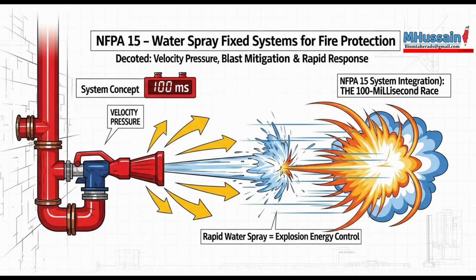It really is. What specific type of event are these UHS systems designed for? UHS systems have a very narrow, specific purpose: the extinguishment or control of deflagrations. That's according to 12.1.1. A deflagration is rapid burning, but the fire front moves slower than the speed of sound. Okay, slower than sound.